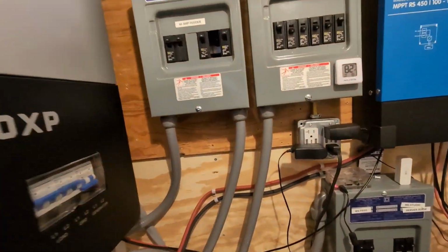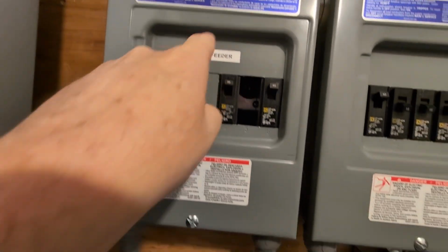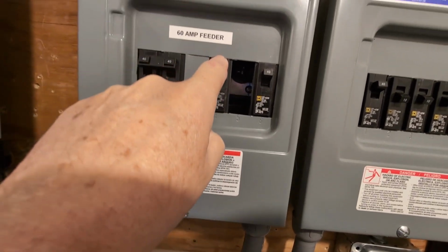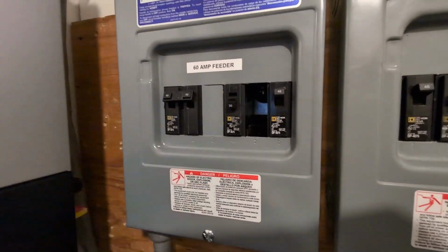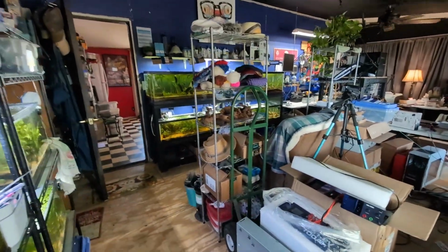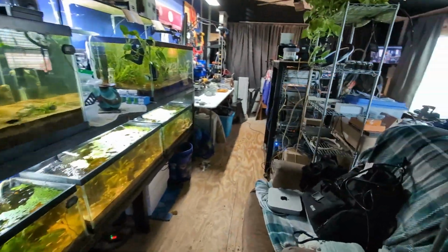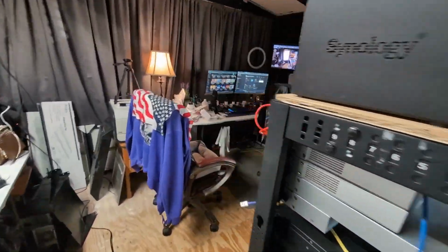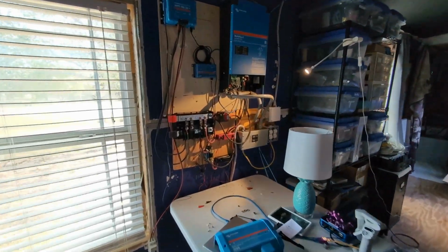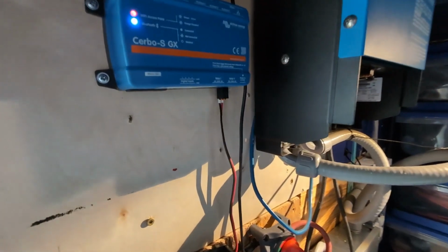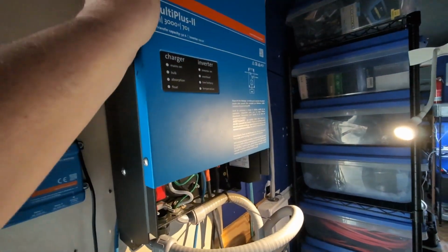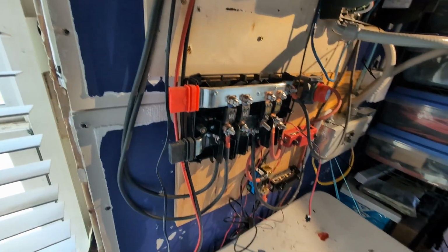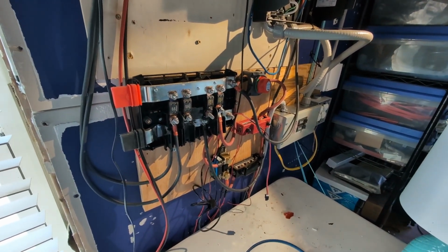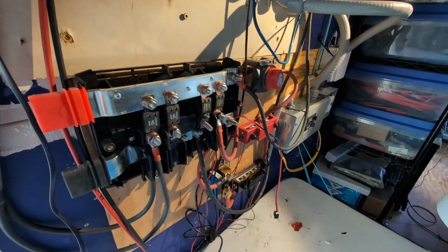So this is the 24 volt 3000, comes through this 30 amp breaker. Once I turn that off, we now have no grid power going to that. That goes on this cable up here, and so now we have no power coming over to this inverter at all, no battery power. I should be able to start deconstructing this mess and making some sense out of it. So we'll go ahead and unplug the servo, it doesn't need power right now. Everything else should be off. The Victron's off. Now we'll get started putting stuff back on the wall and getting this fuse off.